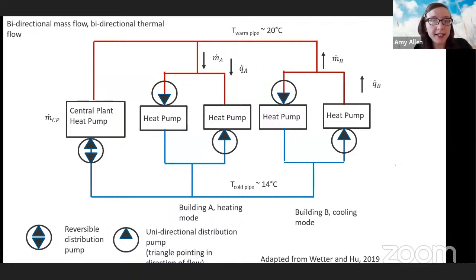And so this design facilitates both bidirectional thermal flow, as reflected in the fact that connected loads, such as the two shown here, will either reject heat to or draw heat from the main loop, depending on the building's dominant load, which in this case will also be reflected in the dominant direction of mass flow in the loop, meaning if there's a dominant heating load in the loop as a whole, the direction of mass flow will be from the so-called warm pipe to the cool pipe, and vice versa if the dominant load is cooling. If the connected buildings exactly balanced each other in load, then there'd be no mass flow through the centralized heat pump, and the buildings' complementary loads would simply offset each other.